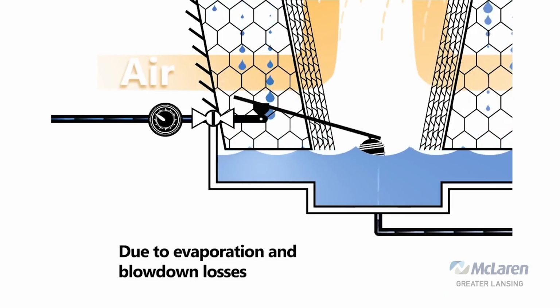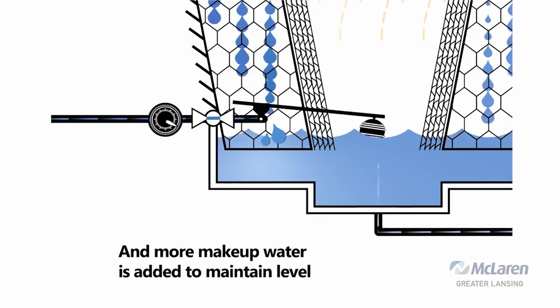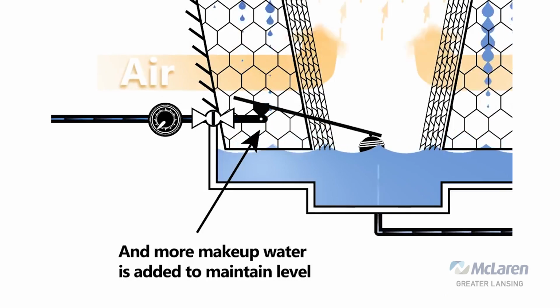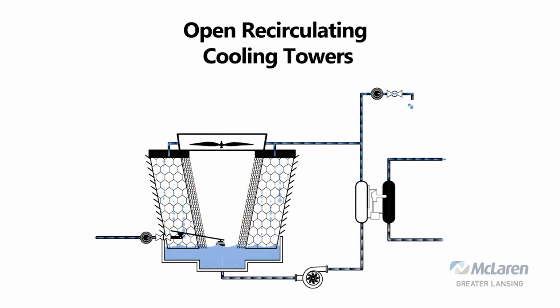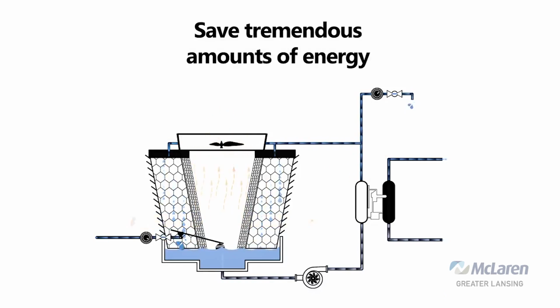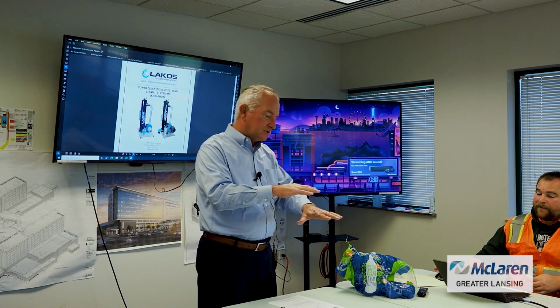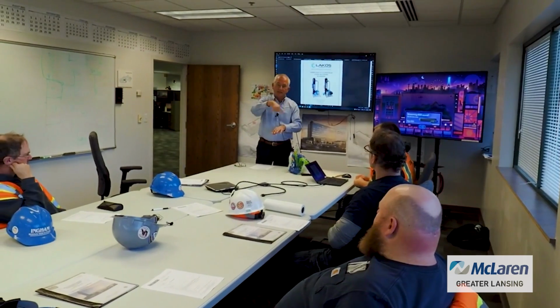The key part of that is, in 4 years, how often had that spray water system been cleaned? Biocides or biological growth was dirt, debris, and crap, right? Because if it's down here and you've got a bunch of crap up here above it, that's the food source, and that's like protection against any biocide you put into the water.